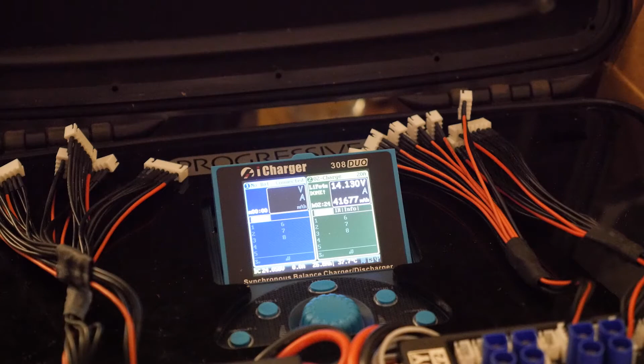I'm going to set this - I got it now set to 300 amps for the shunt. I'm just going to put my devices, the heat gun and everything else, back at what I had it for when it was set to 100 amp. I bet I was actually pulling 24 amps instead of 8 amps. Man, that's probably why it discharged in like an hour and 50 minutes. So I'm going to hook this back up and see how many amps it's actually pulling, to check if this display is right.